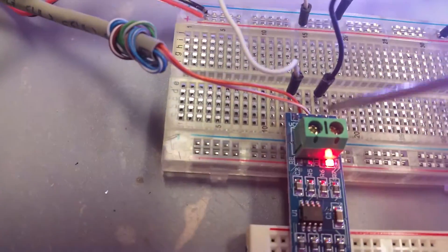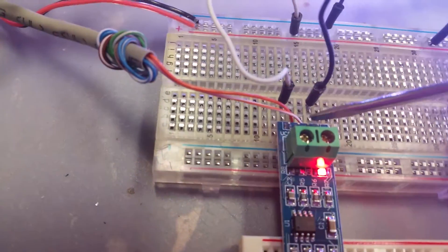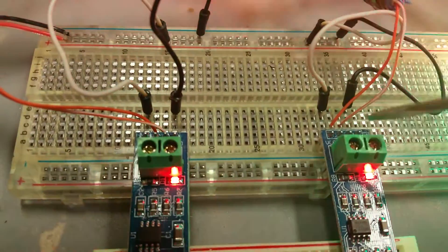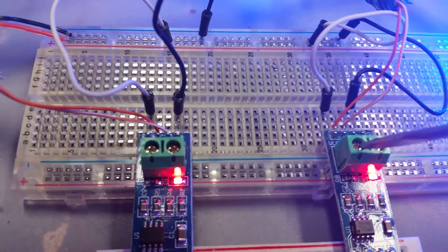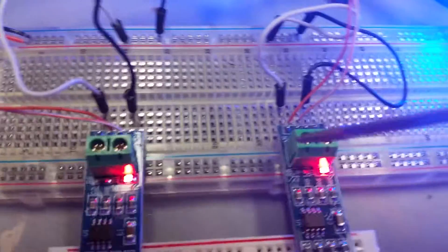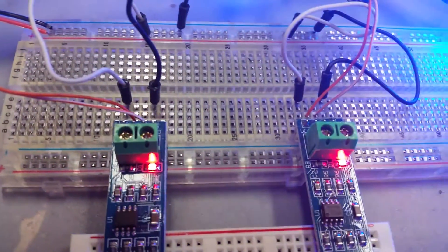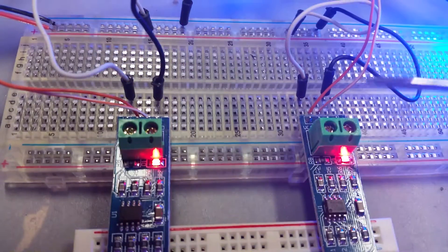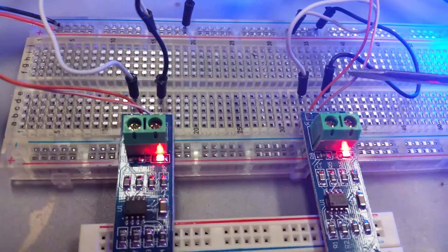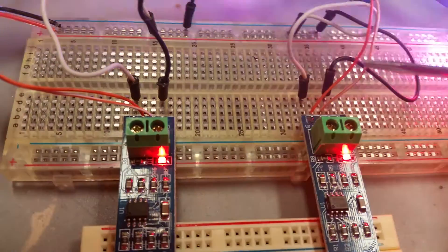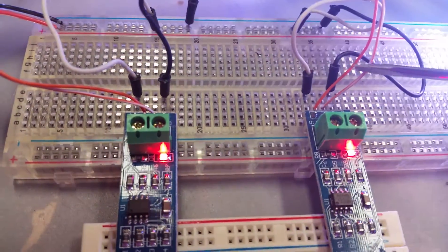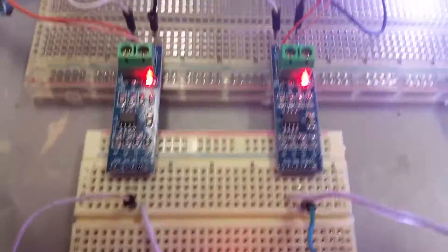I want to make sure you're aware that these A and B lines are balanced. They are not referenced to ground; they are referenced to each other. So you don't ground either one of these. Don't bridge either one to ground or you'll get a corrupted signal out.